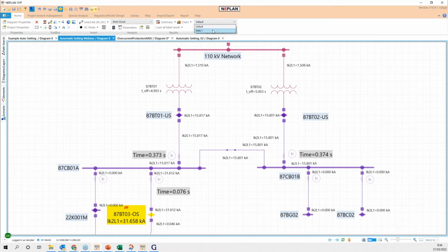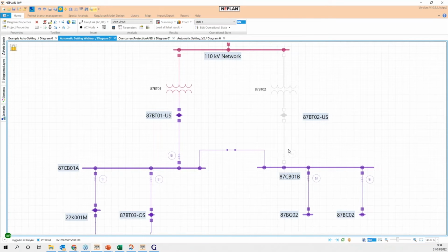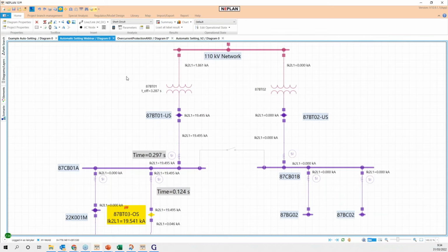But what happens if we have another state where this transformer is open? Or what happens if we open this switch? So we are changing the operation, we are changing the topology. And if we run the simulation, we can see that the tripping time has changed. In that case, we do have selectivity, since this protection trips first, but the delay between both operations is not bigger than 200 milliseconds, which initially was our criteria for this example. That means that we have affected the time delay for the coordination of this system. So NEPLAN allows us to validate that, in different complex networks.